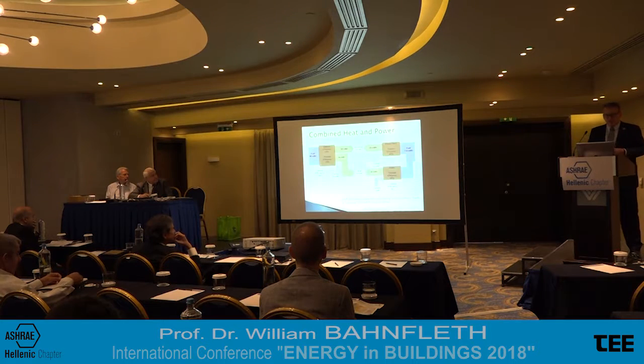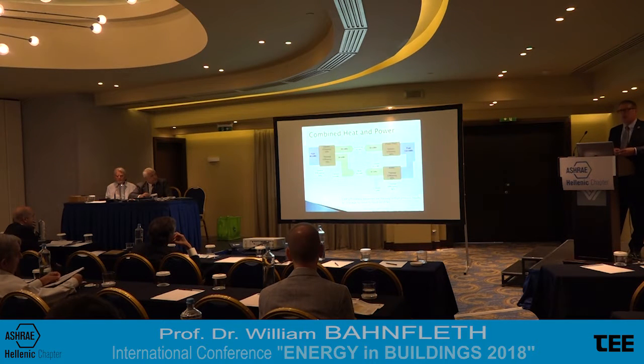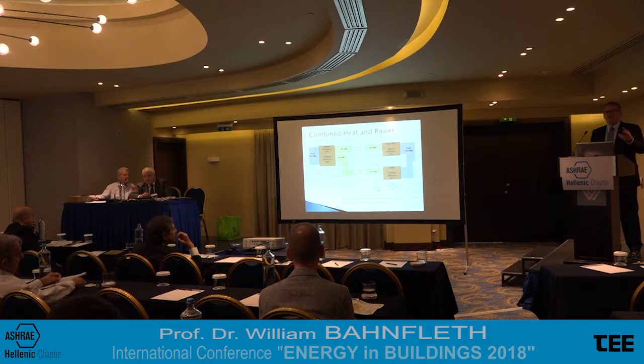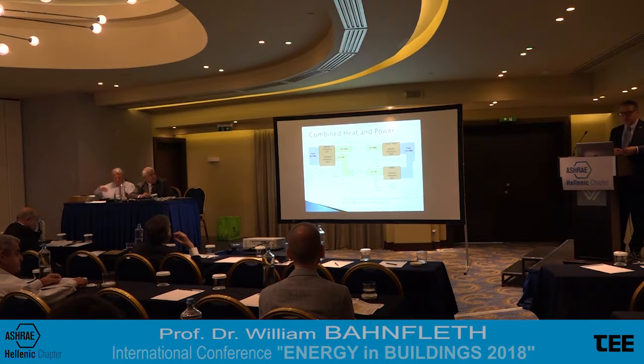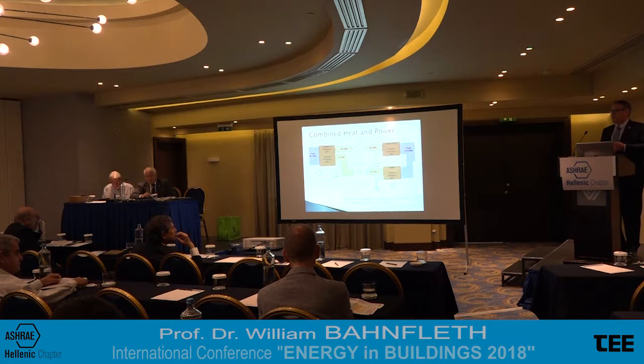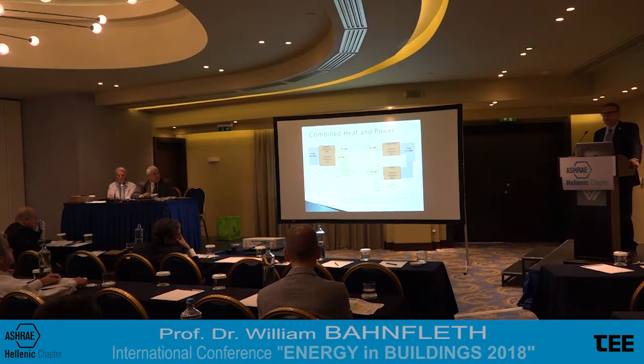And one more example that everyone understands is combined heat and power. We know that if we use an energy source, say to make power and then take the heat and use it for a useful heating purpose, that improves the overall efficiency of the system. So we could go from less than 50% to over 75% efficiency by doing that. The important thing about combined heat and power is the first word, combined. You have to be able to have simultaneous loads to take advantage of this, and they often aren't simultaneous, and we find that using thermal storage is an important factor in maximizing the potential to utilize CHP.